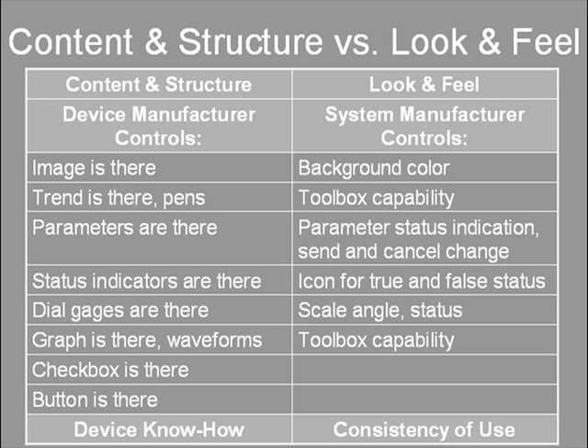There is a difference between content and structure of the device displays on the one hand, and look and feel on the other. The content and structure of the device displays is controlled by the device manufacturer. This makes sense because the device manufacturer knows best what information in the device is relevant and how to make calibration, diagnostics and setup easy. The look and feel of the displays is determined by the software. This makes sense because the controls such as buttons, checkboxes, trends and graphs must work consistently for all devices.